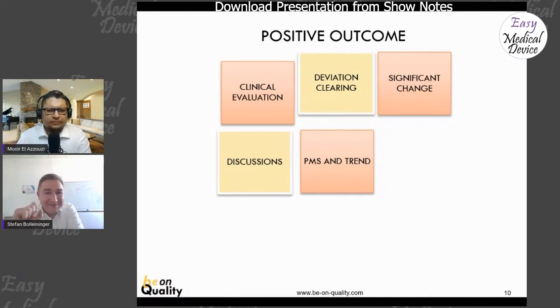This is also something I found very, very interesting in discussion with the notified body - there is guidance for significant change, what it means. However, everyone is still in the position to define for themselves what they mean by significant change. So even when the flowchart suggests every software change will directly lead to significant change, that's not meant with it. You need to negotiate with your notified body what your significant change is, what the needed amount of significant change is, and where you say, hey, until I don't cross that line, all is fine.